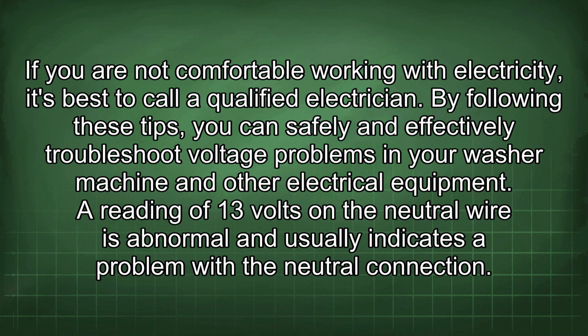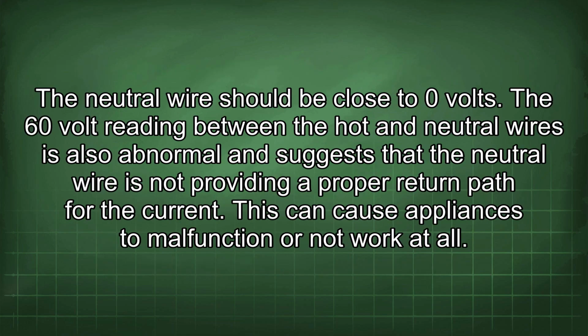A reading of 13 volts on the neutral wire is abnormal and usually indicates a problem with the neutral connection. The neutral wire should be close to 0 volts. The 60-volt reading between the hot and neutral wires is also abnormal and suggests that the neutral wire is not providing a proper return path for the current. This can cause appliances to malfunction or not work at all.